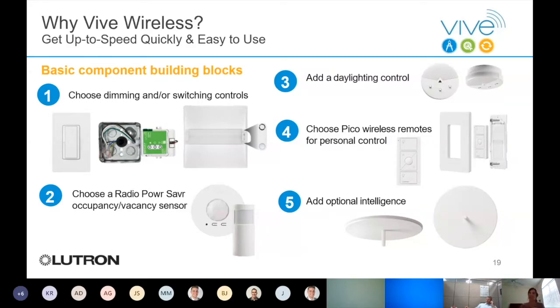Third step: add daylighting. For IECC 2015, a daylight zone with more than 150 watts needs some sort of control on it. This allows for continuous dimming throughout a daylight zone, so when ambient light comes in from that window, you can take advantage of it and dim the lights in the space.